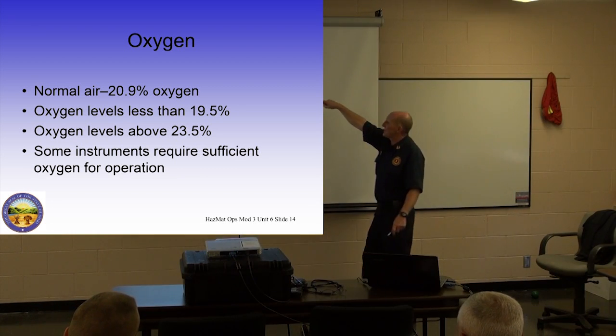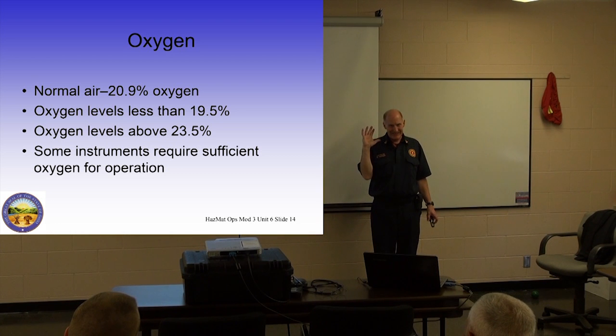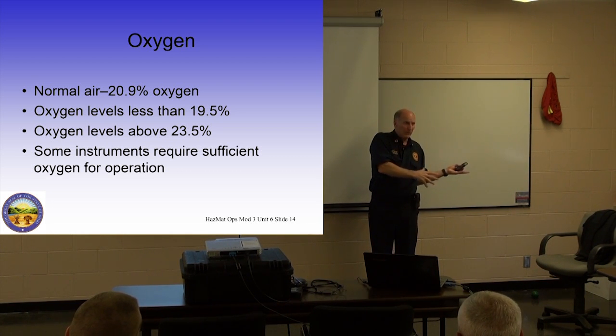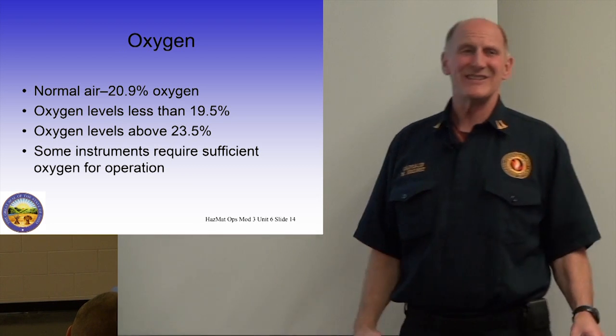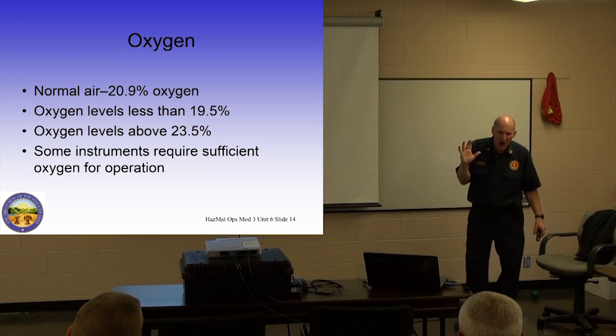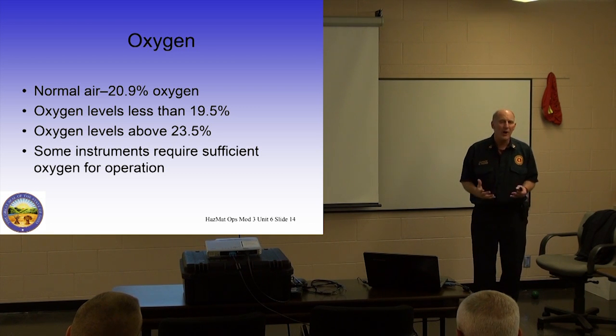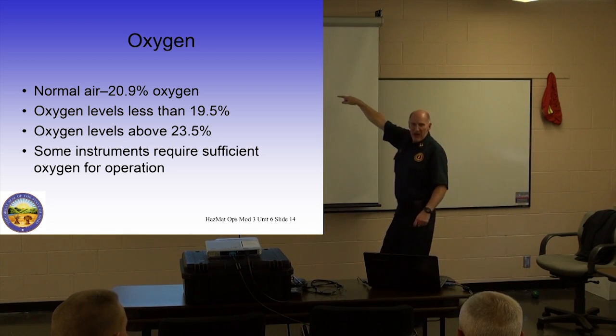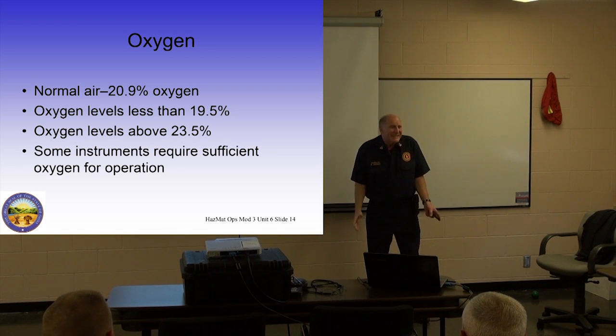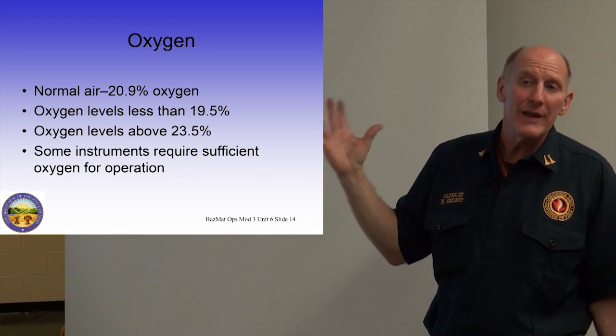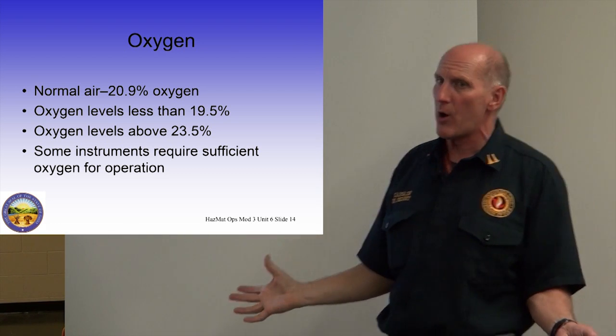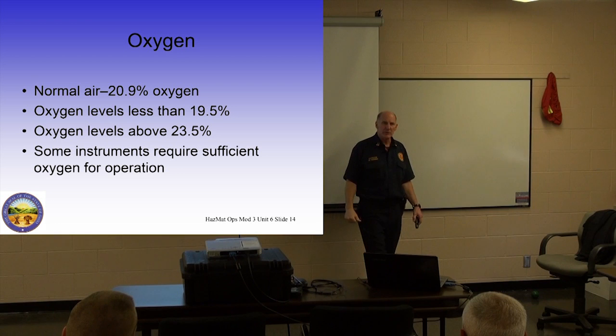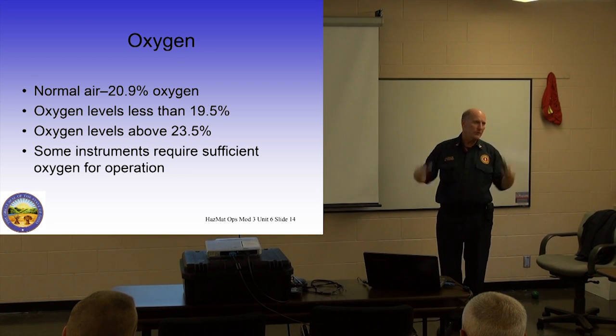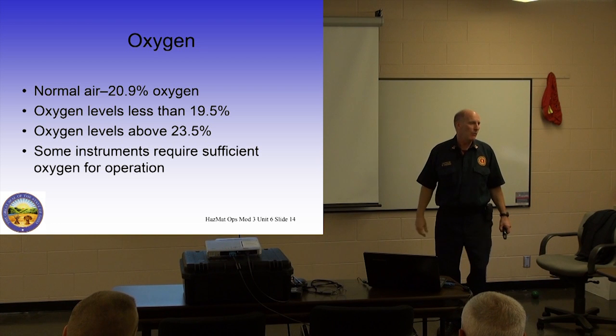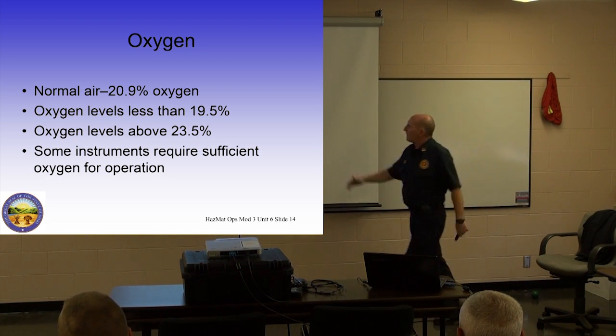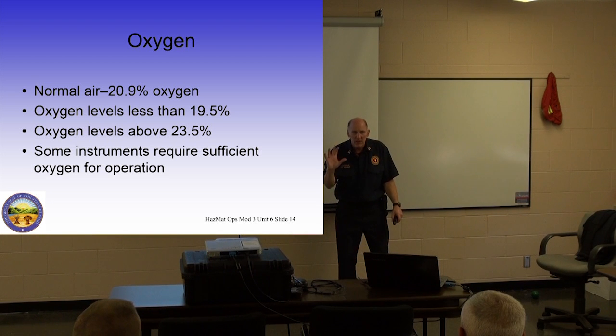The 19.5%, the reason they set that alarm there is, again, because that's the legal requirement and because the rest of the instruments don't work good in oxygen-deficient atmospheres. They will not work accurately. If I immediately drop the oxygen in this room to 19% by adding nothing more than nitrogen, and we all should be aware that nitrogen is not harmful to us, if I drop the O2 in this room to 19%, you guys would hardly know the difference. Troy might find it harder to stay awake. You might be a little bit more tired. But the bottom line is 19% O2 ain't going to kill anybody.